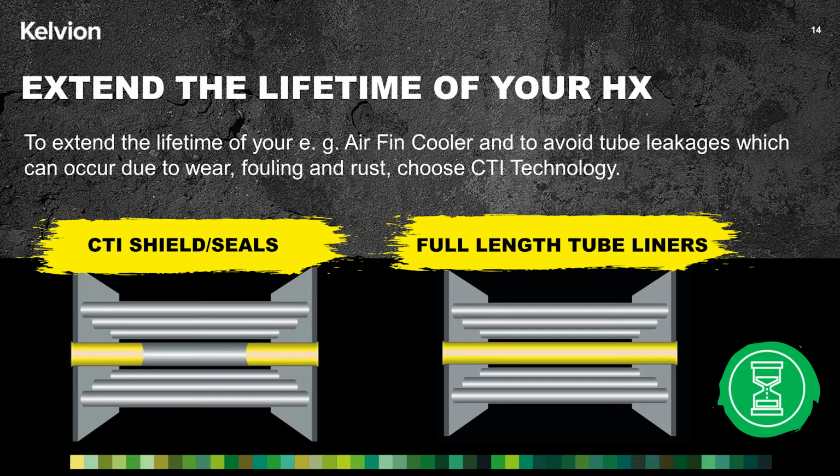The second solution is what you can see on the right-hand side. Full-length tube liners are designed to restore tubes that are suffering from corrosion, either pitting or stress corrosion cracking. Those damaged tubes that in the past might require you to plug them are now returned to service. Liners can reduce fouling and increase efficiency over plain carbon steel tubes. Tube liners are designed into new heat exchanger builds to increase reliability and extend service life expectation.